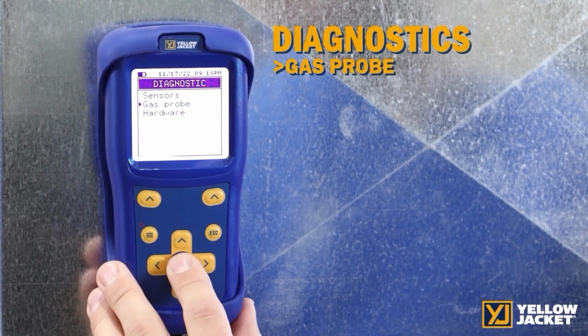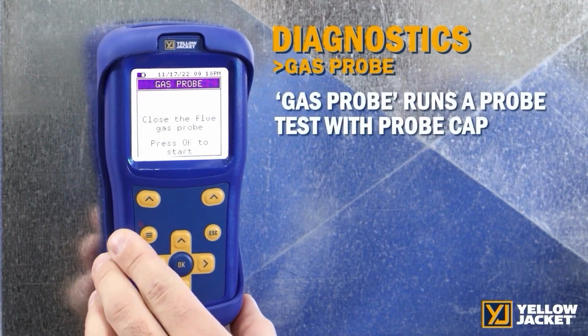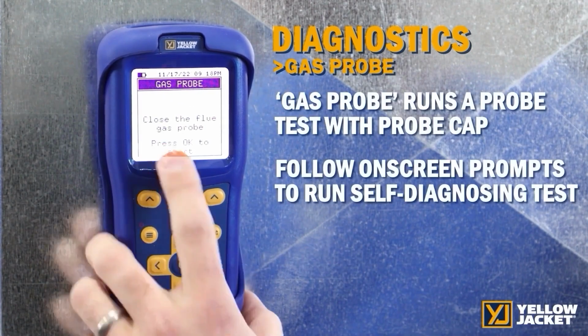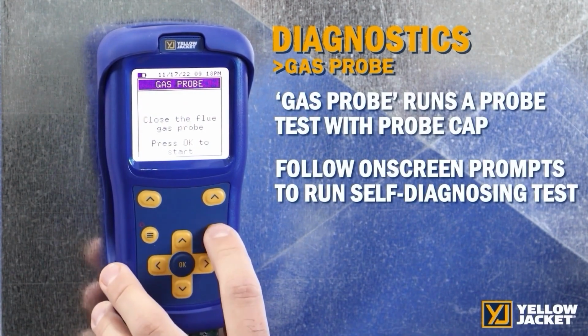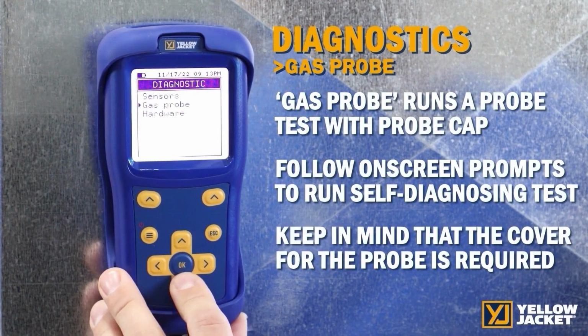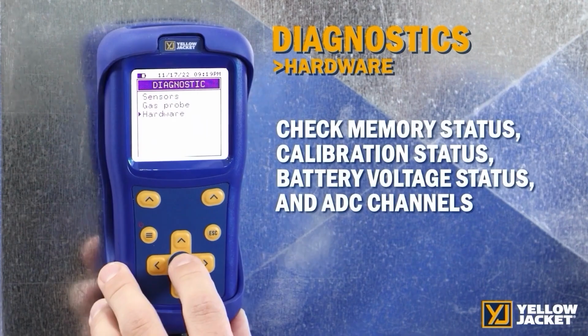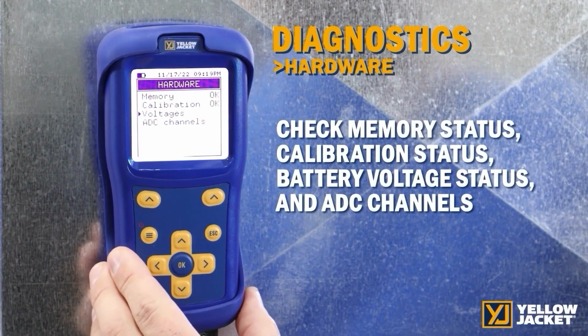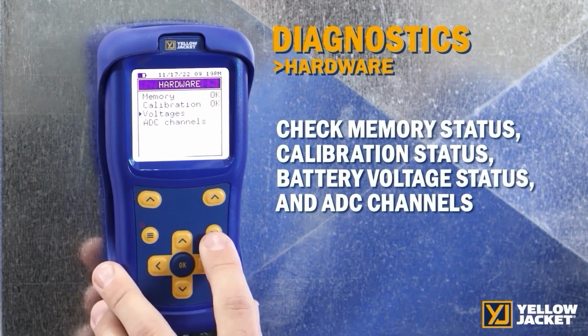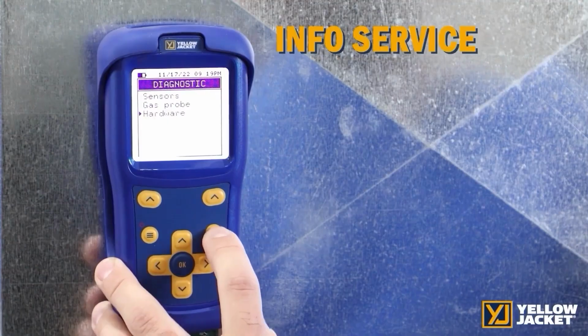Gas Probe runs a probe test with probe cap. Follow on-screen prompts for running this self-diagnosing test. Keep in mind that the cover for the probe is required for this test. In the Hardware menu, you are able to see the memory status, the calibration status, and the battery voltage status, as well as the ADC channels.